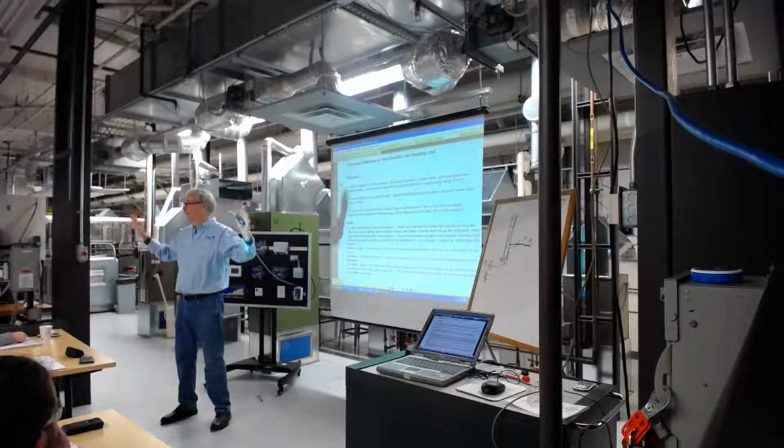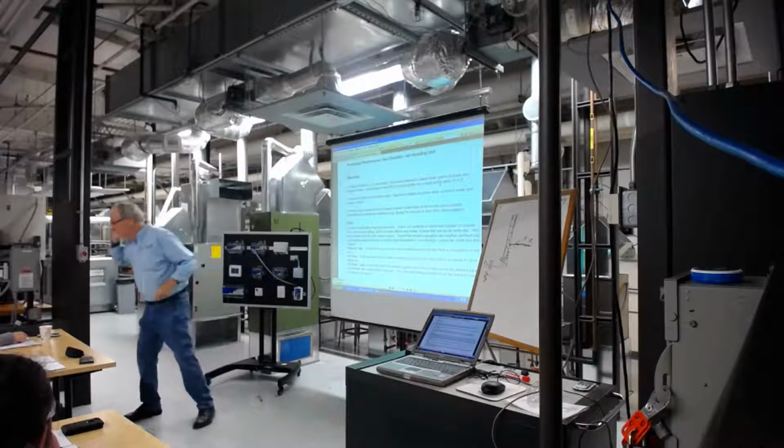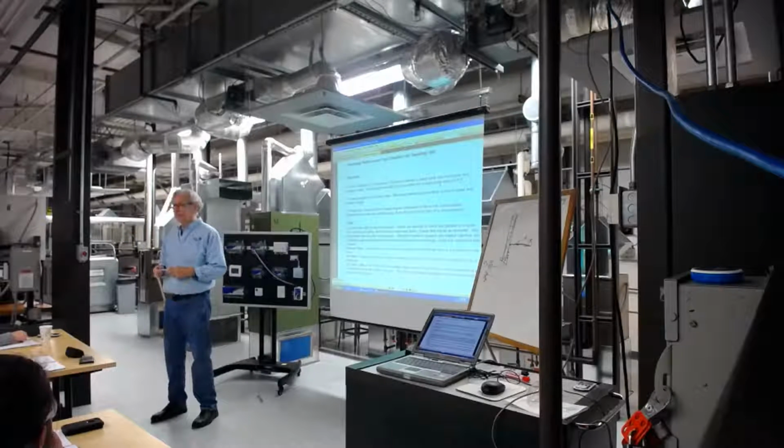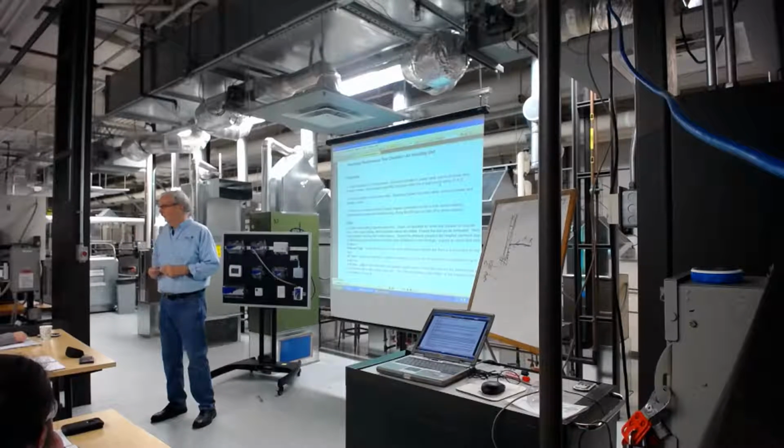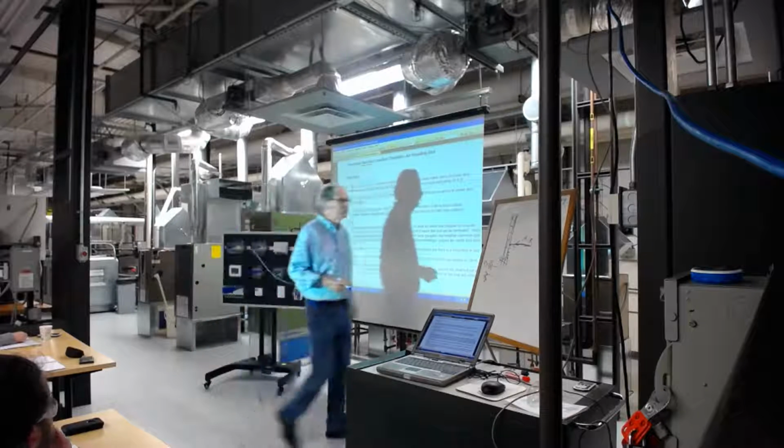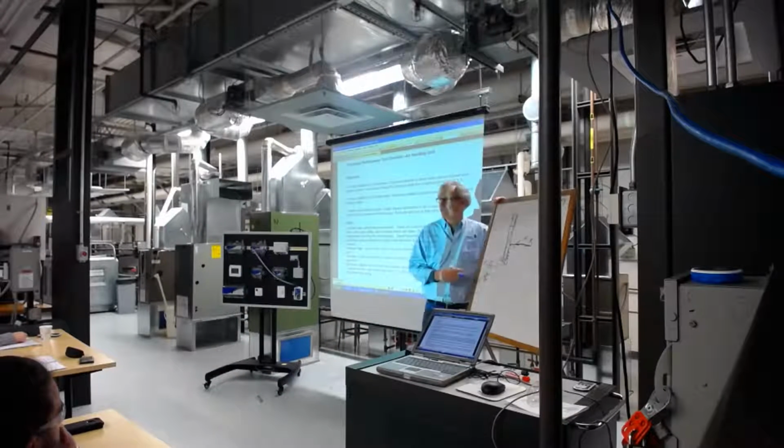Think about the big picture now. Think about the central plant. Yeah, the compressor's going to work harder, right? And that means you went below design. Design was 45, you went down to 43. The chiller can do it, but it's going to start doing a lot more work.